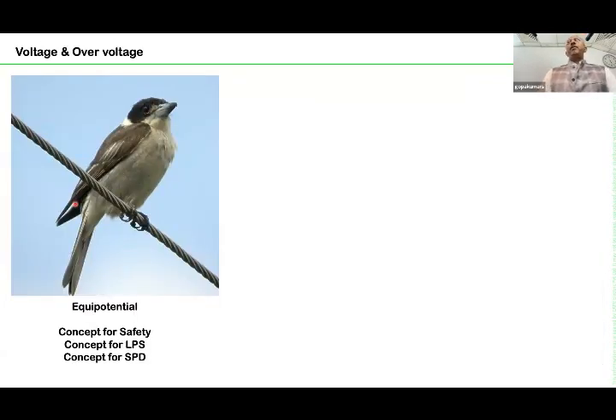Now, with respect to safety, the fundamental concept is equipotential bonding. That means during the transient condition, during a short time, once when there is a problem in the installation, or once when there is a lightning or a transient situation, potential differences should not exist between conductive parts. That is the basic idea. You have to make every metal part at the same potential as close as possible.